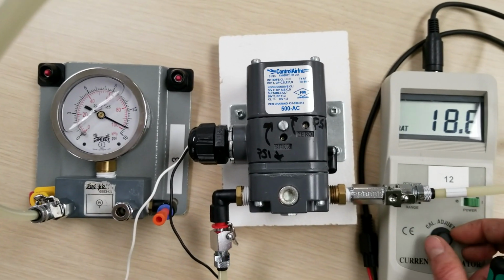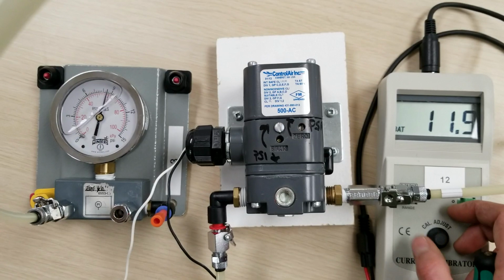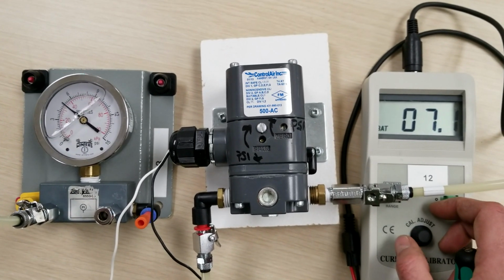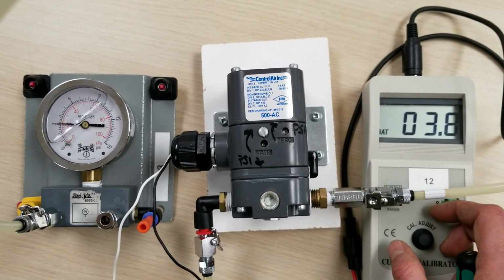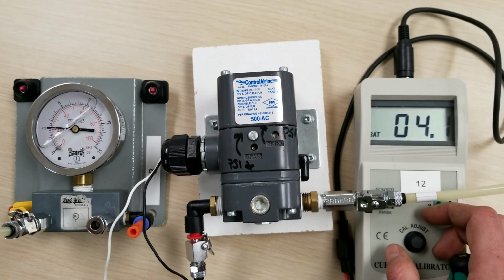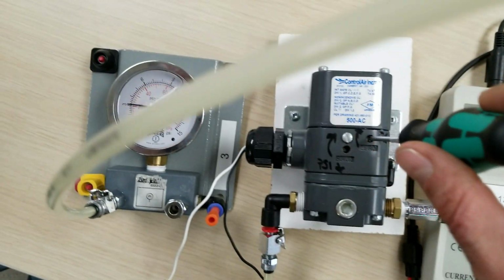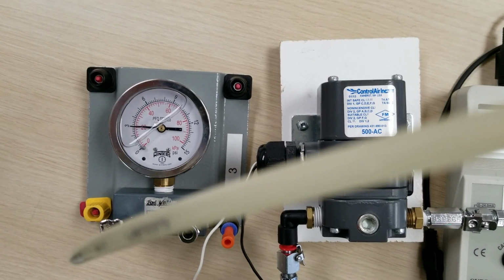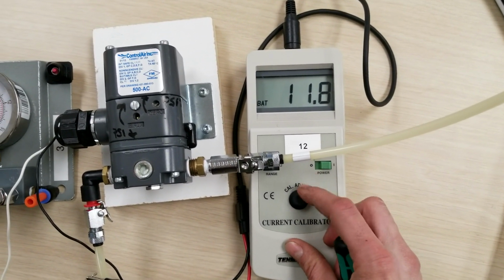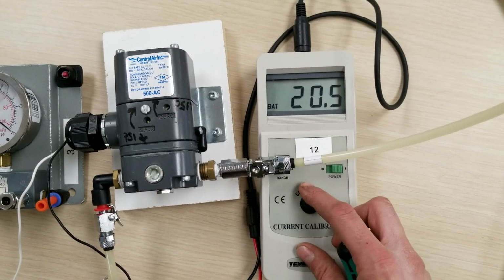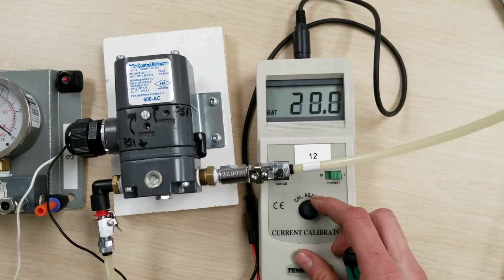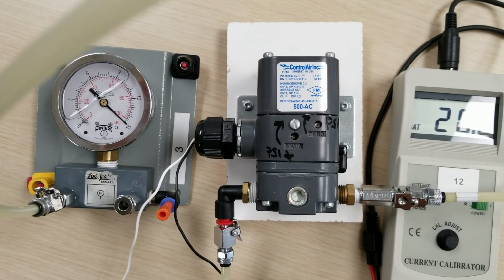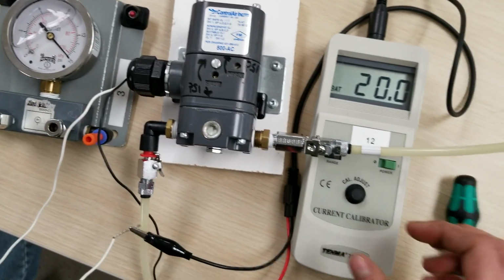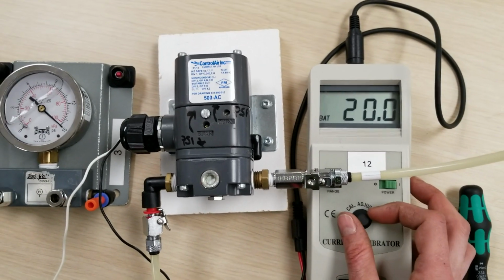So one more time. We'll bring it down to 4 milliamps. And we're still close to 3 psi. Adjust my zero again. See, sometimes you need to tweak it a few times. Looking pretty good. Another thing we can check is if we have the right pressure to current through our range.